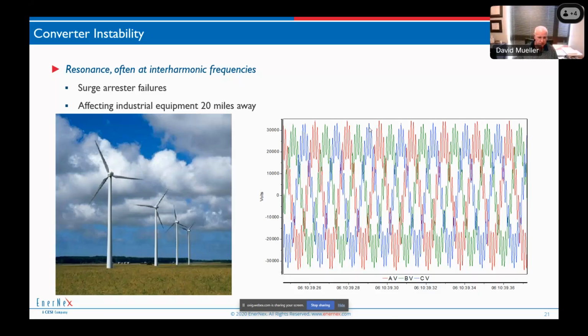I've seen about a dozen cases. I've seen cases with wind turbines. I've seen cases with type 3 wind turbines. I've seen cases with type 4 wind turbines. I've seen cases with full conversion wind turbines, as I said, and also inverters. For whatever reason, it hasn't been as prevalent in inverters as I thought it would be, because it seems like most of the major manufacturers of wind turbines had at least one case of this, to my knowledge. But inverters, we haven't seen as much of it. So I don't know if there's something different about the way the current controller loop makes it a little more sensitive, but maybe we're getting past this problem of converter instability.